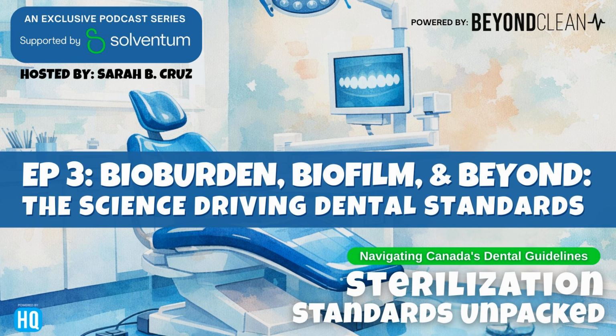A very important point was about type 5 or type 6 chemical indicators. For implantable parts, which mostly happens on the dental side, type 5 and 6 are required. Type 4 gives limited information, type 5 mimics the biological indicator response, and type 6 is defined for only one specific cycle, so if our cycle changes, we have to use another type 6 defined for that specific cycle.